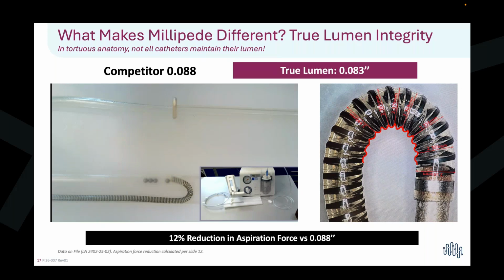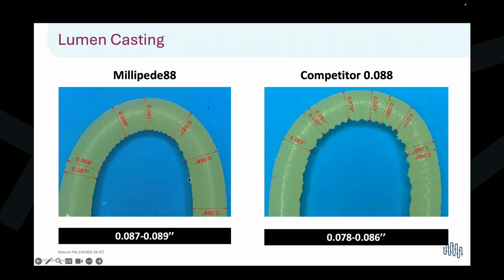And so this is also visualized when you cast the internal portion of the catheter and then see what that looks like. And so if we cast the inside of a millipede with luminal casting, you can see that it maintains this 088 diameter pretty much throughout, even in the areas of highest tortuosity. However, if we look at a competitor, a typical 088 catheter, which you can see here is in the area of maximal tortuosity, there's enough kinking whereby you lose a significant portion of the internal diameter. It goes from 0.088 to 0.078.